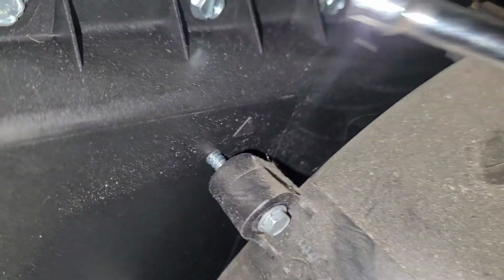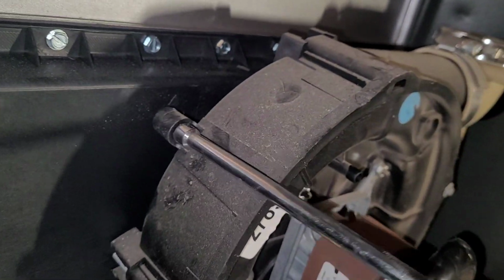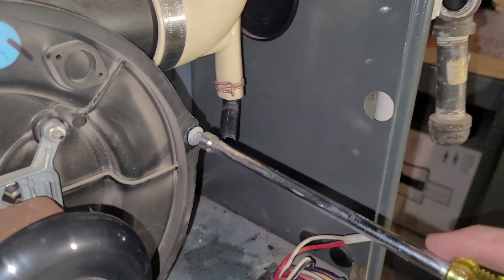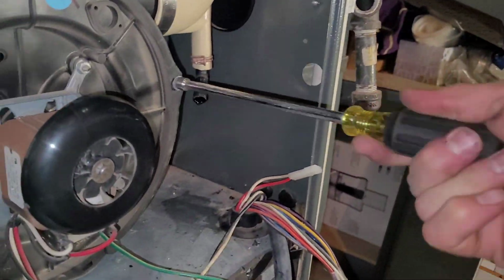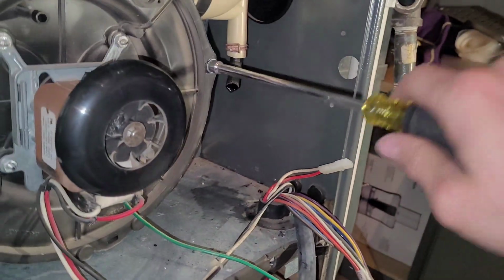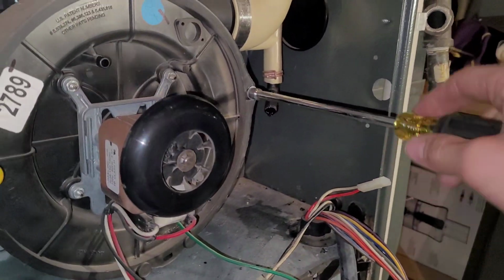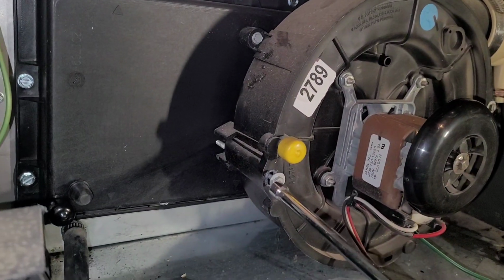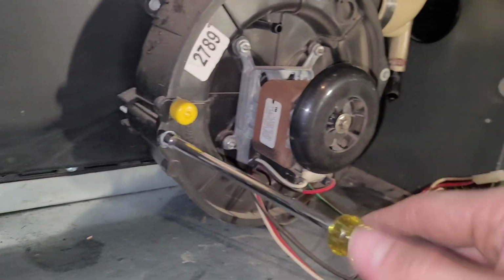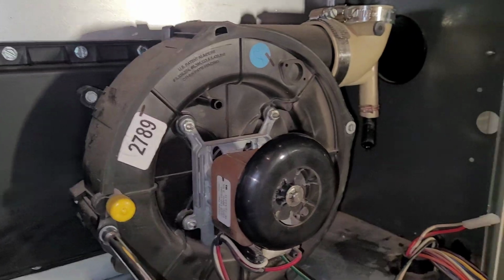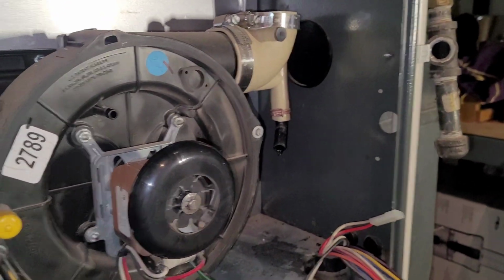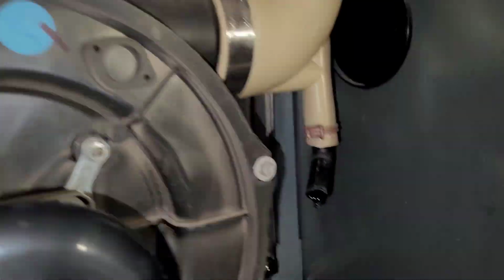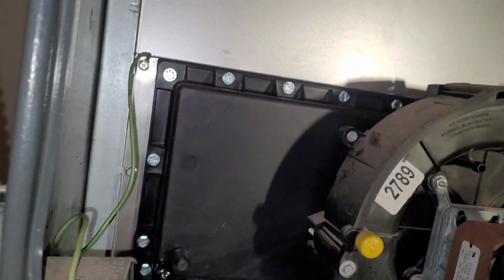These screws that hold the combustion blower in are just going into a small hole with no threads cut in it in the collector box, so I like to do these ones manually by hand because I don't want to strip them out. They're easy to strip out, and if you do strip them out, it ruins this collector box and you have to buy different ones, so it's worth running a few of these in by hand. Of course, the other screws can all be run in with an impact within reason, obviously. But none of these holes have any thread cut in them, they're just stamped, so you have to run the screws in. Of course, it's just a matter of reassembling.